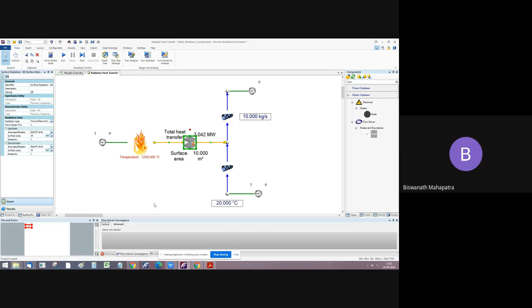Then here we have the calculation. As I mentioned, first we go to the model, then the calculation. The total amount of heat gained by the water after the radiation heat transfer takes place is calculated by the formula m Cp dT. m is the mass flow, Cp is the specific heat of water, which is 4.187, and dT is the temperature difference. It enters at 20 degrees Celsius, and after gaining heat from radiation it becomes 92 degrees Celsius. By this formula, the heat we get is 3.04156 megawatt. Here we will apply the Stefan-Boltzmann constant.